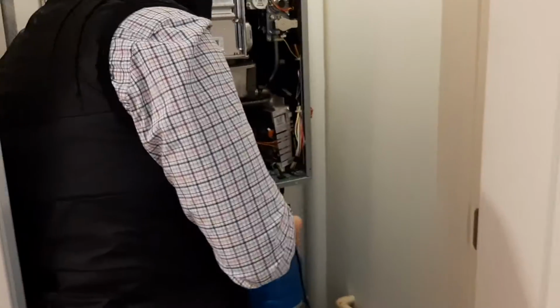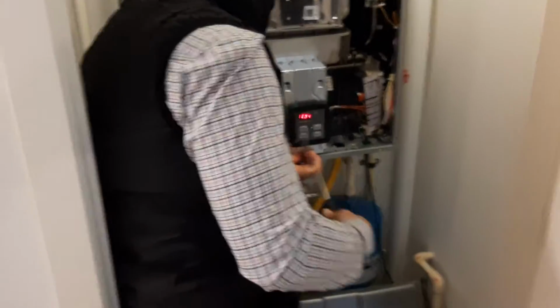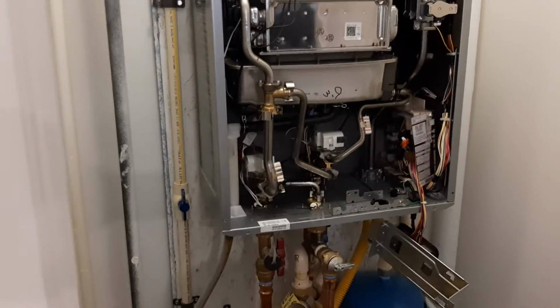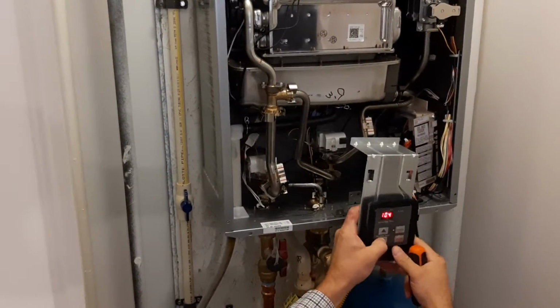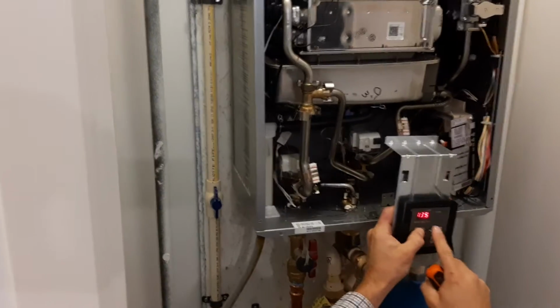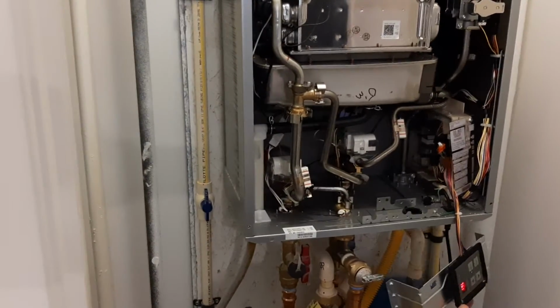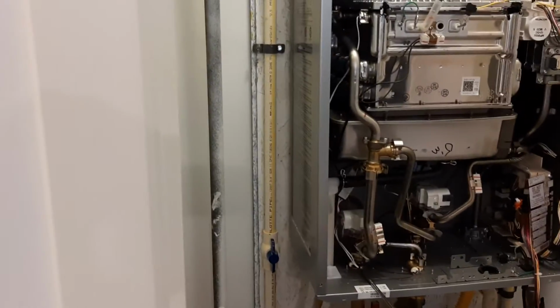This might be a little too technical, but I like to give more info, and if you don't need it, you don't have to look at it again. Here's how the unit operates: let's get this control out of the way. When cold water comes into the unit, it knows it has to get to whatever temperature you set the controller for. 140 degrees is what they should all be set for, so it wants to reach 140 at that sensor.